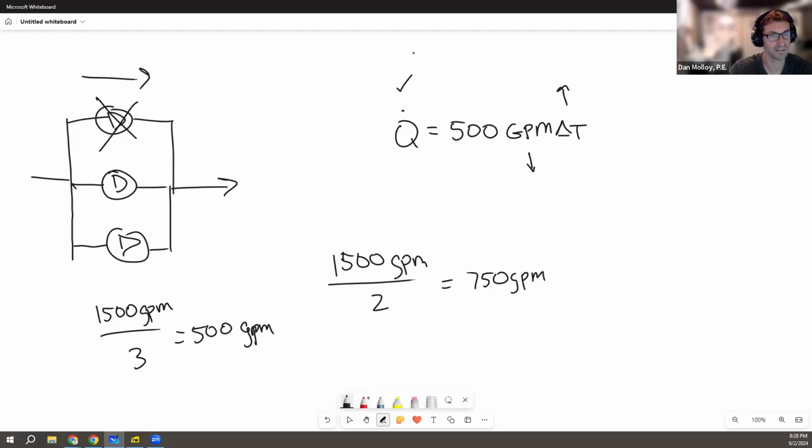And we don't have any reason to believe that we're allowed to mess around with the temperatures here. Maybe the chiller's maxed out. Maybe it's doing all it can. So we're not being specifically told that we can take a 10-degree delta T and make it 30% or 50% larger. So in the absence of that, we have to assume that that needs to be held constant as well, which means we can't have a lower GPM.